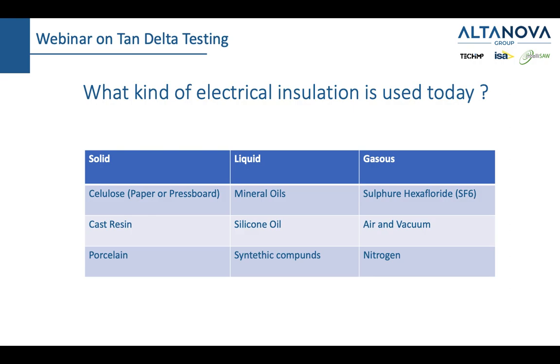Apart from that, we also have liquid insulation like mineral oils, silicone oil, which is more expensive than mineral oil, and all types of synthetic compounds, which are usually used with power transformers to insulate and also cool down the transformer, the windings, the core, etc. And then we have gaseous insulation, for example sulfur hexafluoride, often used since the 1930s, air and vacuum, or nitrogen.